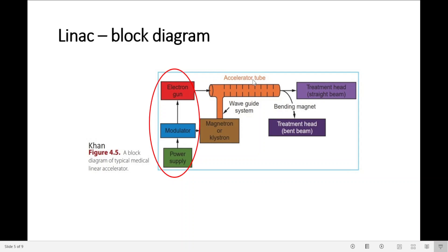In the accelerator tube, the electrons are accelerated by the high power microwave towards the treatment head. When the electrons exit the accelerator tube, they are in the form of a pencil beam, with approximately three millimeters in diameter. And they are high energy electrons.